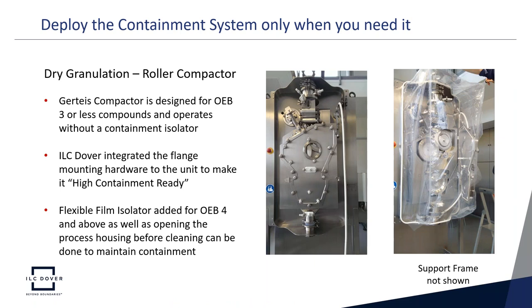Another example involves a roller compactor common in dry granulation workflow. With Gerteis, a compactor design easily delivers OEB3 containment for a range of compounds without a containment isolator. By integrating a containment flange mounting to their system to make it high-containment ready, the flexible isolator can be deployed to achieve OEB4 or OEB5 processes. This is valuable not just for high-OEB compounds, but also because the roller compactor process housing must sometimes be opened, where the flexible containment provides critical additional protection.